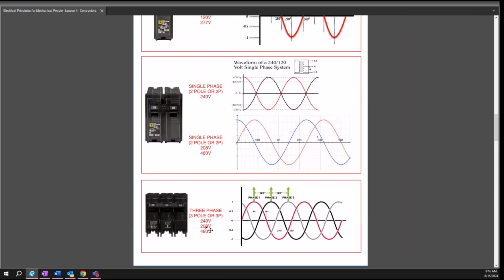And if you're not using every single pole, it is single phase, even if you're using the higher voltage. Doesn't mean the panel isn't a three-phase panel, but the connection itself is single phase off of the three-phase system.